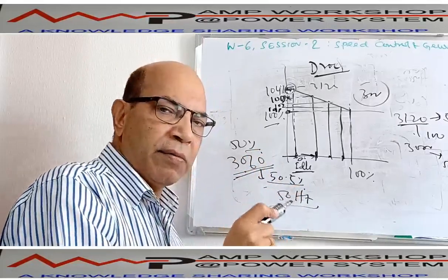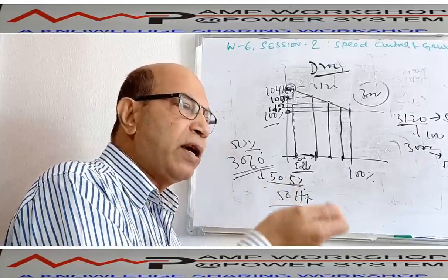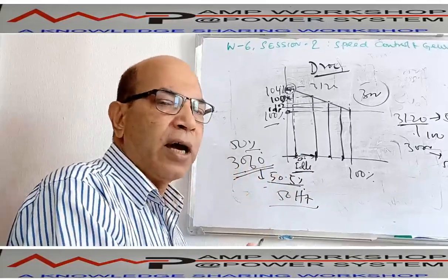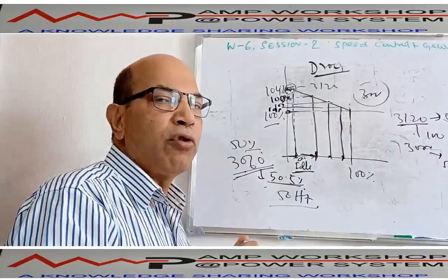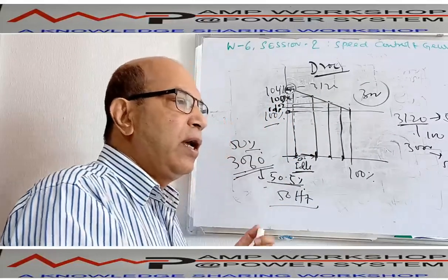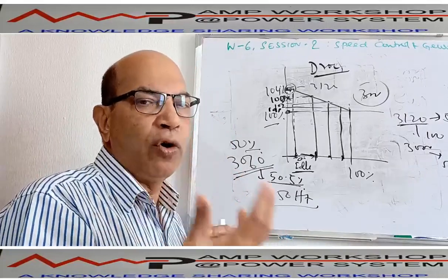Now after running the operator will be observing the frequency of the bus. Now he has to come back and control the frequency manually to bring it back to the required frequency. So if the machine is operated in this way, then we call it droop mode operation. The advantage of this droop mode operation is that how much load a machine will take depends on its own droop setting.